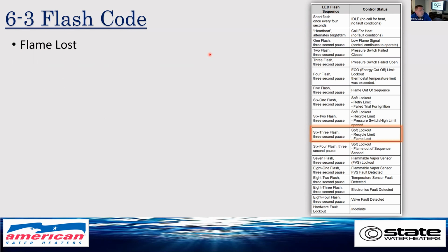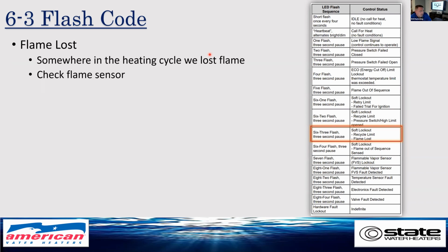A 6-3 flash code: flame lost. Somewhere in the heating cycle, we lost flame. Again, we're going to check our flame sensor. So we're going to cycle our heater again and see where the trouble starts. So that falls back into that sequence of operation. If you know the sequence of operation, you can troubleshoot and figure out what step you lost.